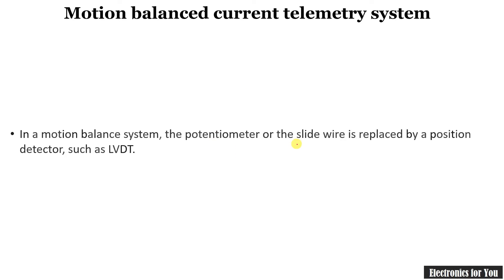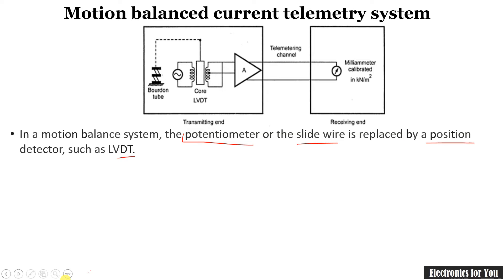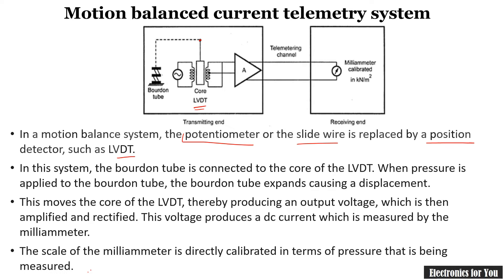In the motion balance current telemetry system, the slide wire potentiometer is replaced by an LVDT. The core of this LVDT is connected to the Bourdon tube. Whenever pressure is applied, the Bourdon tube will try to expand, resulting in the movement of this core. The output voltage of the LVDT is directly proportional to the change in displacement. As there is expansion in the Bourdon tube, there will be a change in position of this core, so the output voltage is directly proportional to the movement, and the change in current is directly proportional to the pressure applied.